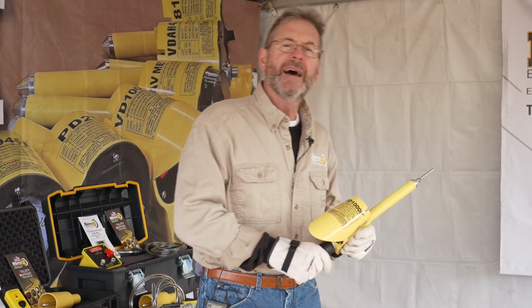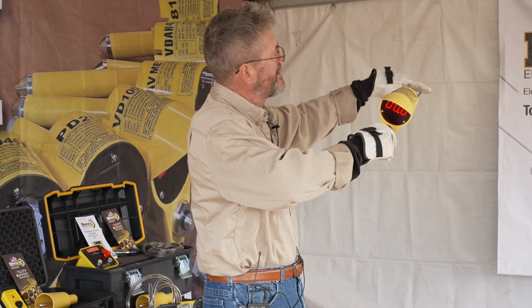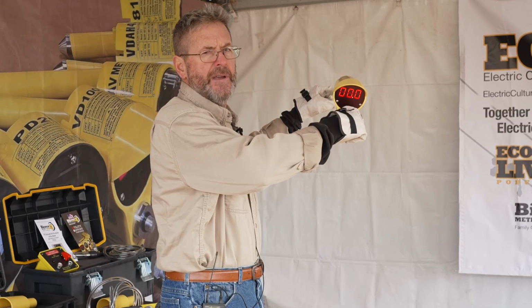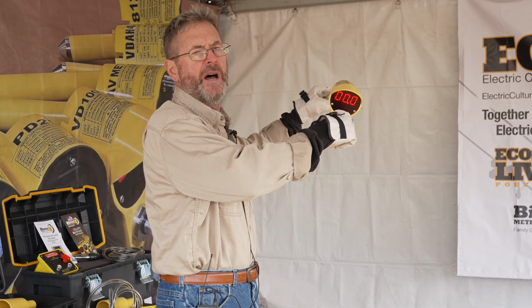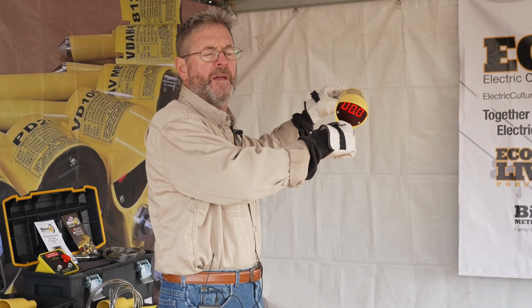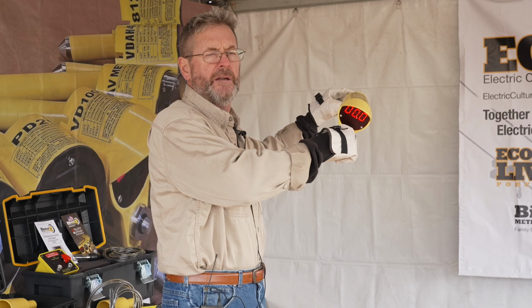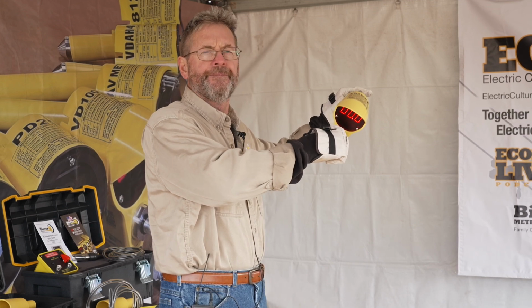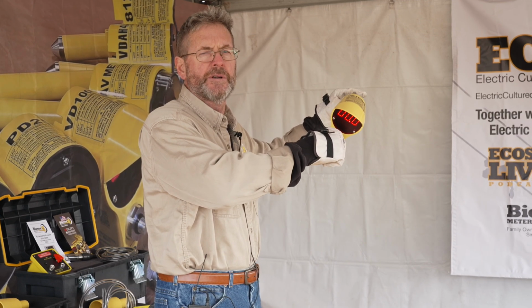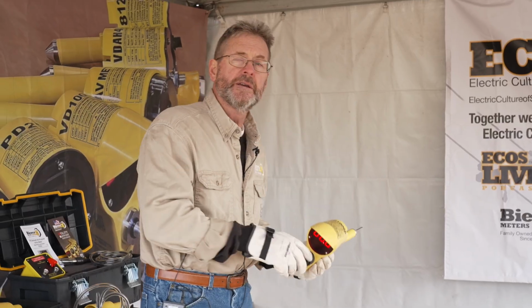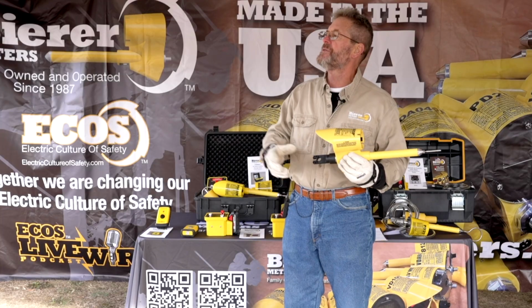Then we go to that line, that conductor, and make contact. As you can see, that conductor is de-energized, so there's no backfeed, no induction, and no system voltage. So what you're going to do is verify the tool is telling you the truth.